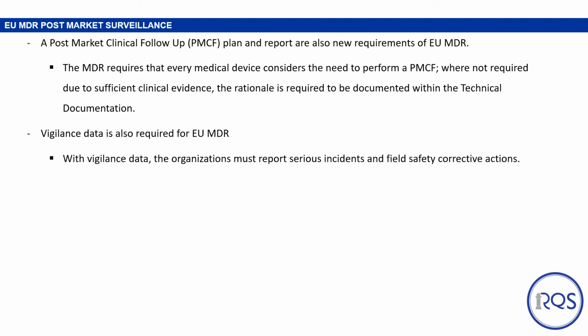A post-market clinical follow-up, or PMCF, plan and report are also new requirements per EU MDR. The MDR requires that every medical device considers the need to perform a PMCF. In the event that there is sufficient clinical evidence, a rationale can be documented within the technical file as justification for not having a PMCF. Vigilance data is also required for EU MDR. With vigilance data, organizations must report serious incidents and field safety corrective actions.